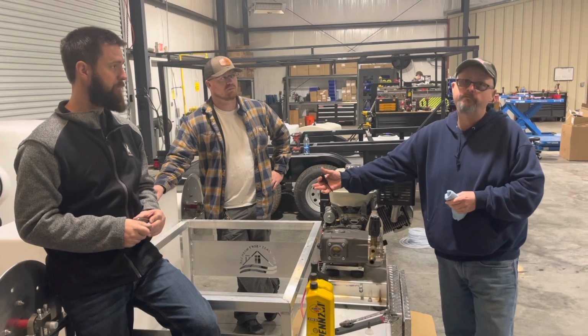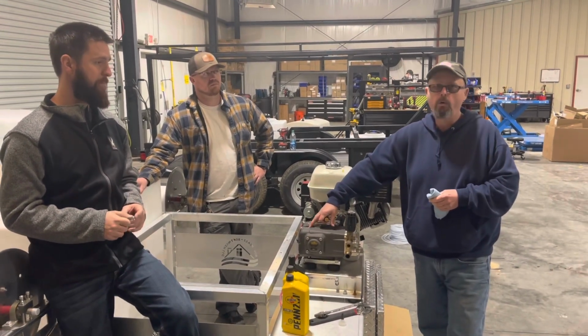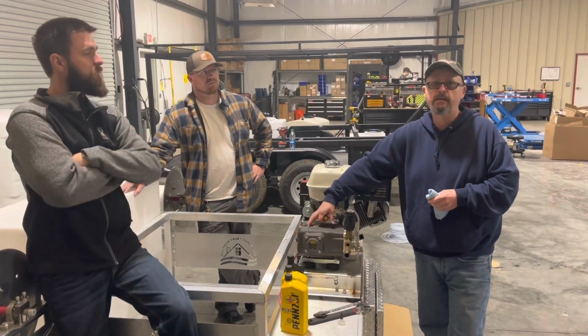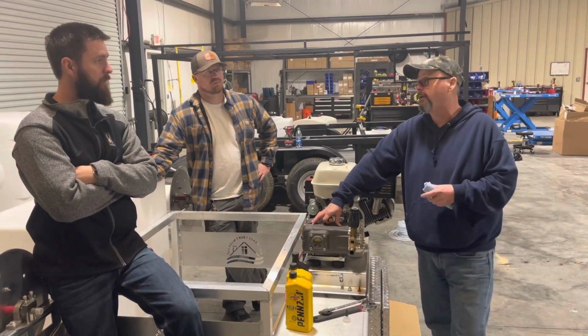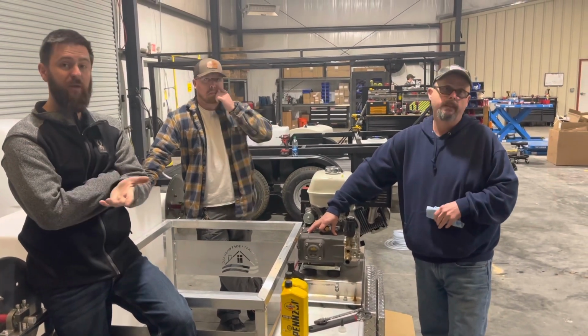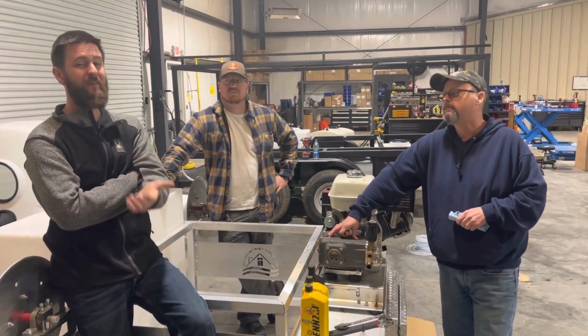That happens four or five times. Next thing you know, it looks a little milky in there. The oil level hasn't drastically changed, but yet your oil has now turned to what we call a milkshake. Right. It looks just like that picture. That was a severe version in that photo, but it can maybe not look quite that bad.